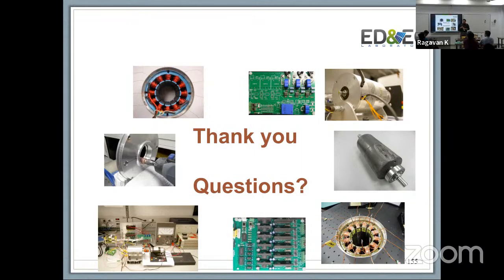Like the companies, basically voltage injection, a current injection, those are actually fairly acceptable practices, depending on what you're creating. So in some scenarios, for example, if you're applying current to an unenergized phase for one of the motors, you might end up creating negative torque. So the question really is, how much torque are you generating?